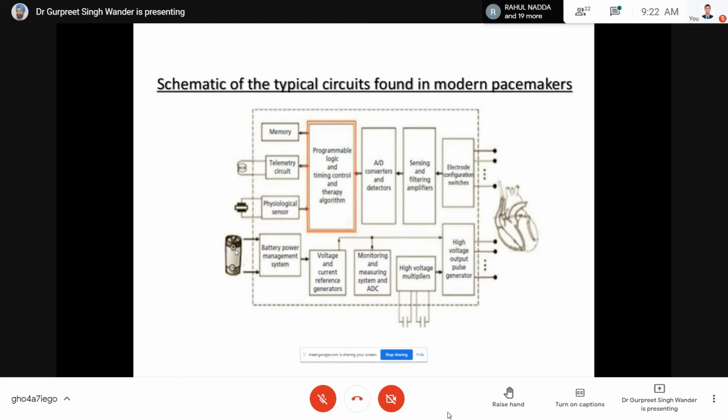In between, nuclear powered pacemakers came a couple of decades back, but there were radiation hazards with those, although they lasted for a longer time. So this is one area which is a research area, actually: how to empower this small pacemaker so that its battery lasts longer. There are some pacemakers now which last for 12 to 13 years also, but that's about all.